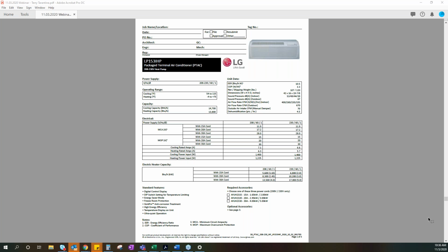And what they've done here is, if you look at the unit data to the right, you'll see that the EER is 10.5. This is a significant gain in energy efficiency, but they were able to maintain that 42 by 16 footprint. So we could retrofit existing systems to these higher efficiency and, more importantly, much, much quieter hotel units. So this is something that we're going to see a trend towards.